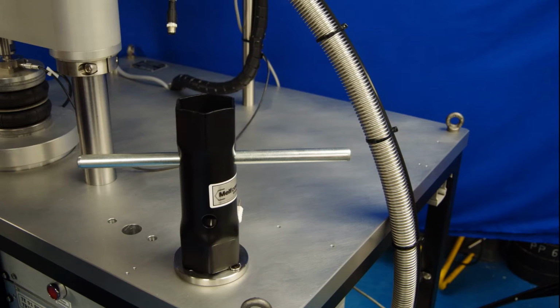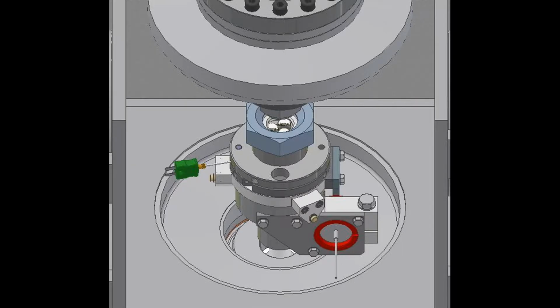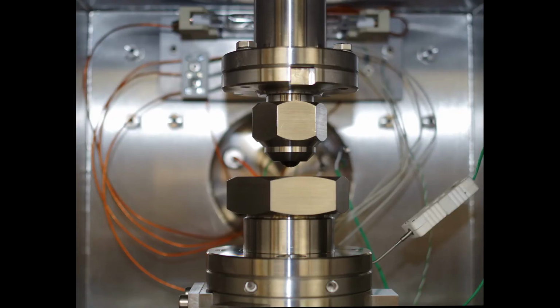Add test oil or grease as required. Mount the ball cup on the heater pad and ensure that the assembly sits flat on the pad. Connect the thermocouple lead to the thermocouple socket 1. Now the machine is ready to run a 4-ball test.